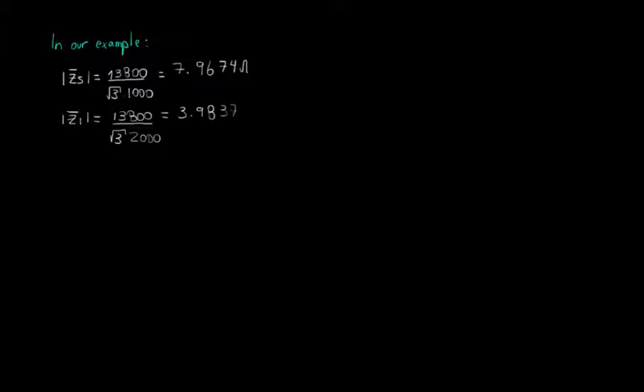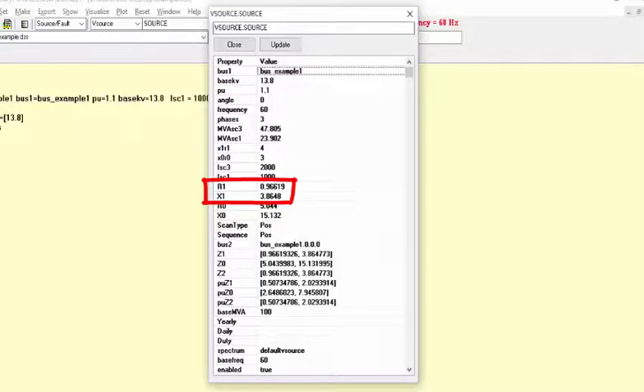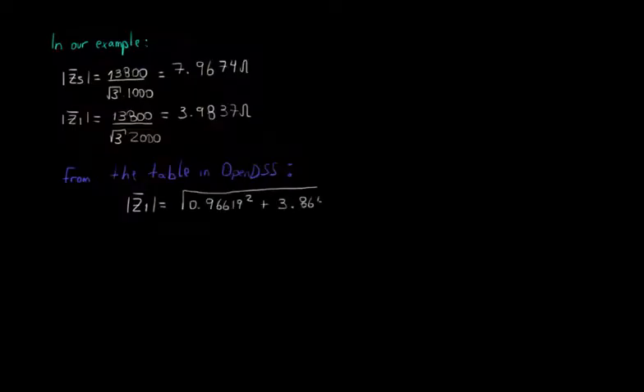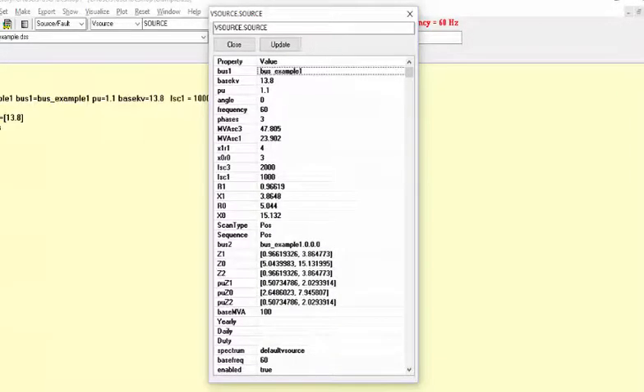Let's take our example as a demonstration. Applying these two expressions, we get that the module of ZS is equal to 7.9674 ohms and the module of Z1 is equal to 3.9837 ohms. From the table in OpenDSS, by taking the calculated values of R1 and X1, we can find that the module of Z1 is exactly equal to 3.9837 ohms, as expected. However, the value of the module of ZS is not shown in the table, as you can see. To check its value, we have two options.